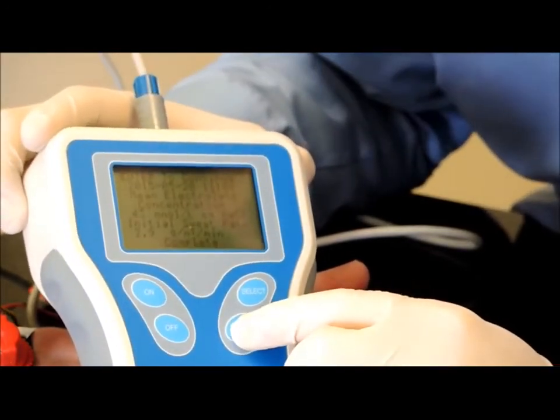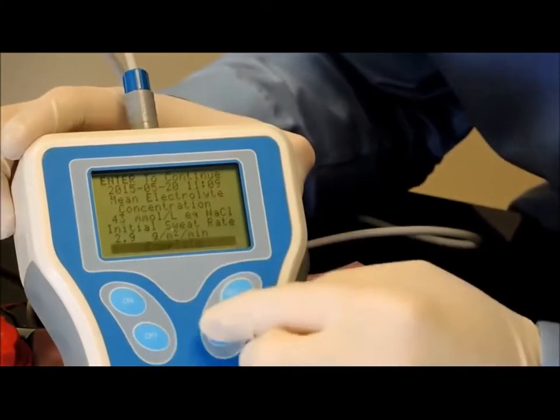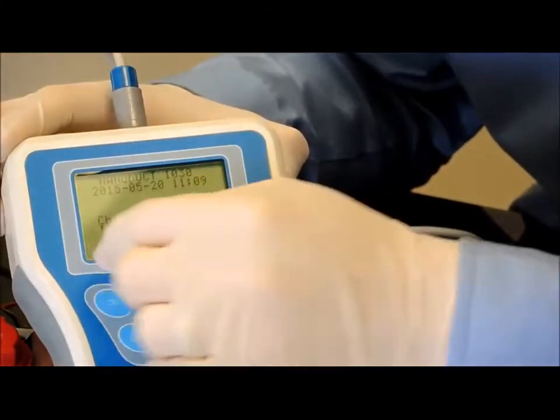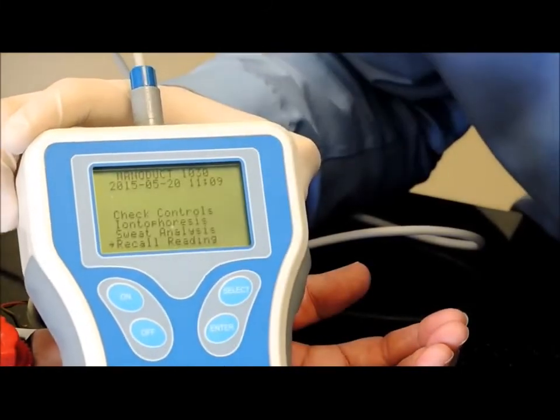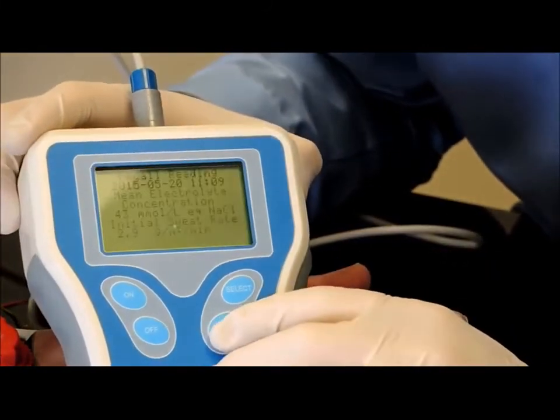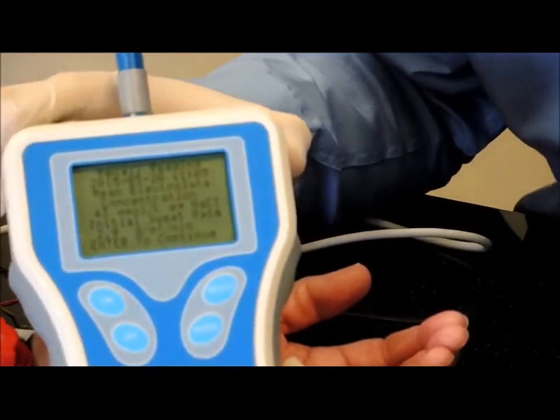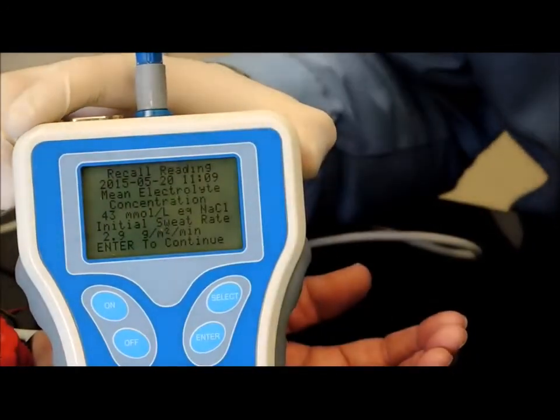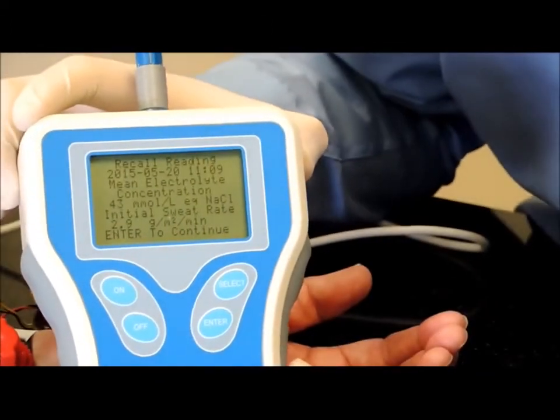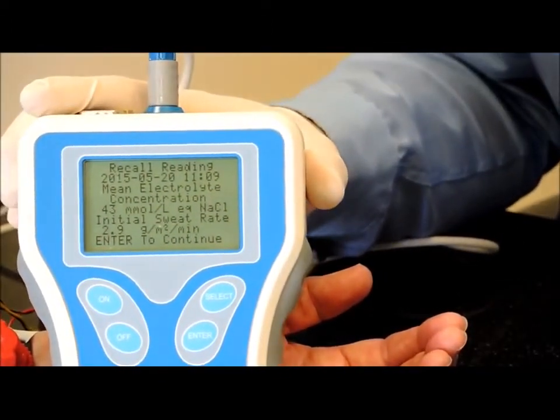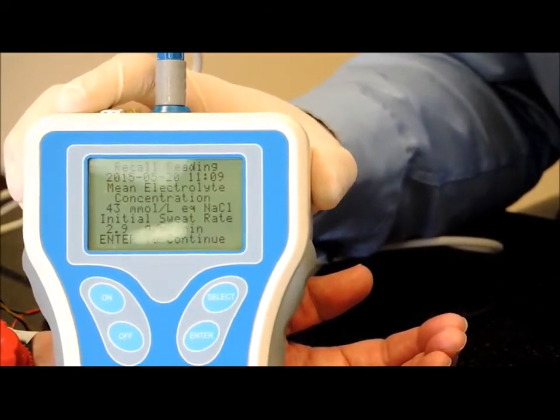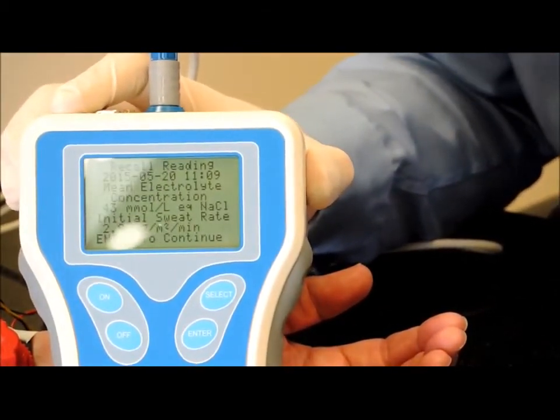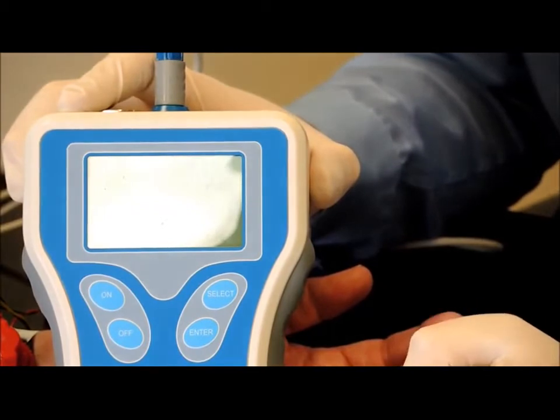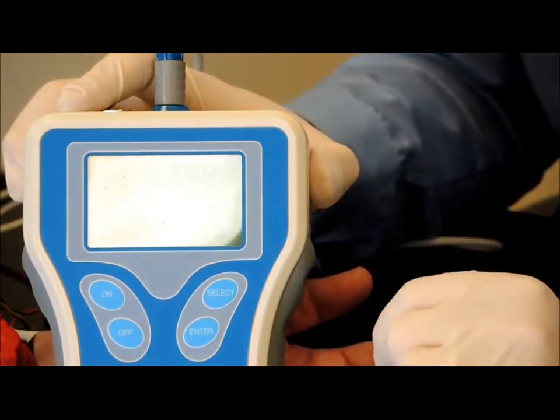So you press enter, and it takes us back to the main screen, and you'll see an arrow that says recall reading. I press enter on that, and it will give us the final reading. Her final value was 43, again with a sweating rate of 2.9. So that's the value that you would report back to the doctor for the sweat conductivity test. That recall reading is important because if you had suppressed the values, that's the only way that you can get that value back.